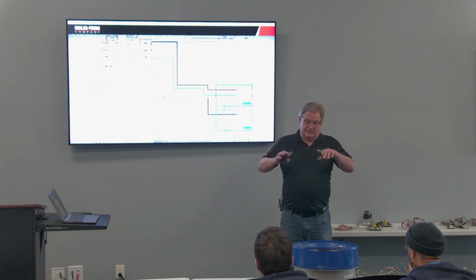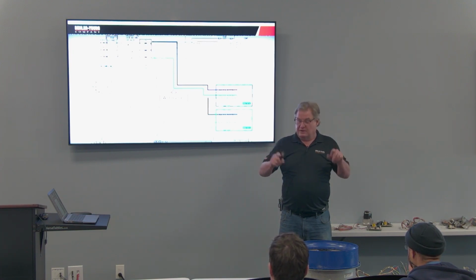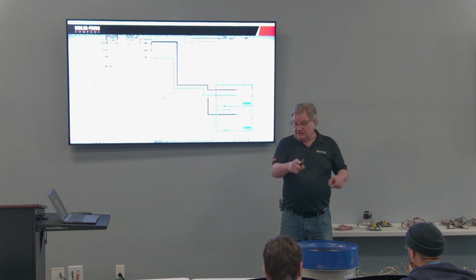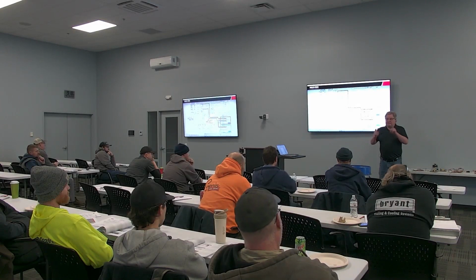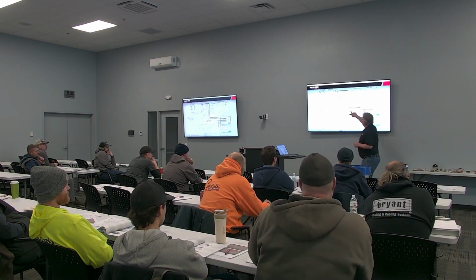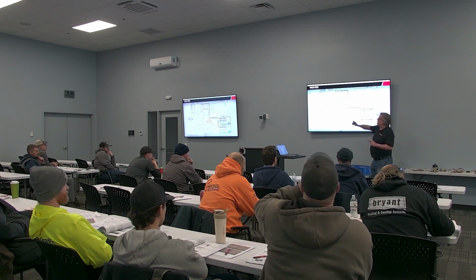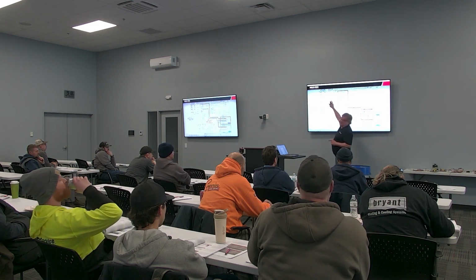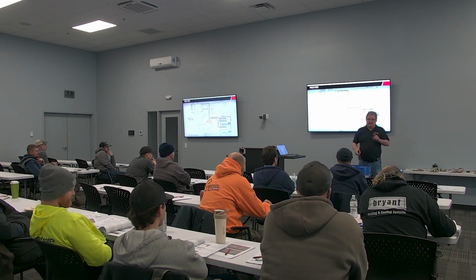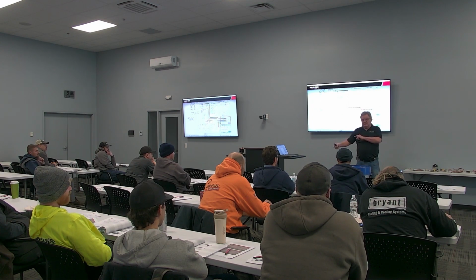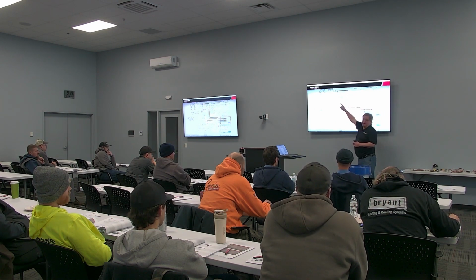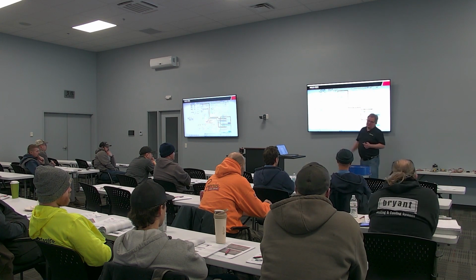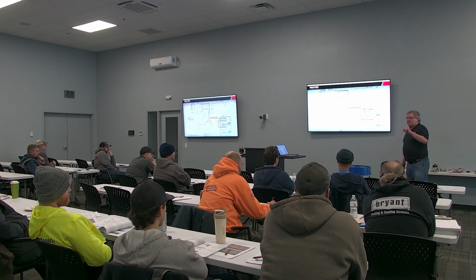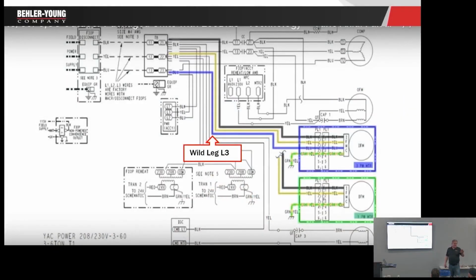So if you are used to looking at your blower motor to see if your compressors are spinning the right direction, you're doing the wrong thing, because that's going to spin the right way no matter how many times you swap the phase. So if you've got the wild leg on L2, you're going to go to your disconnect and swap L2 and L3 to put the wild leg on L3. And then you're going to swap L2 and L1. Why? Well, the first swap reversed my compressors. The second swap would put them back. So is everybody following what I'm talking about? Because when I swapped one of the two legs to put the wild leg from 2 to 3, I just reversed my compressors. So now I've got to swap 2 and 1 to put them back. Run them to make sure you've got them in the right direction. Okay. Is everybody following? Yeah.